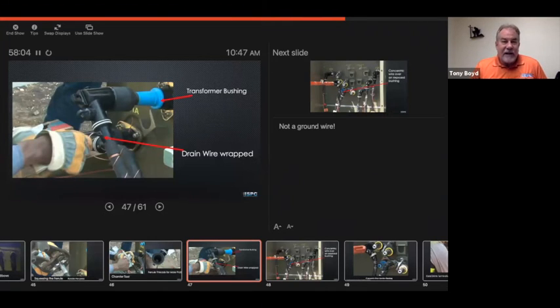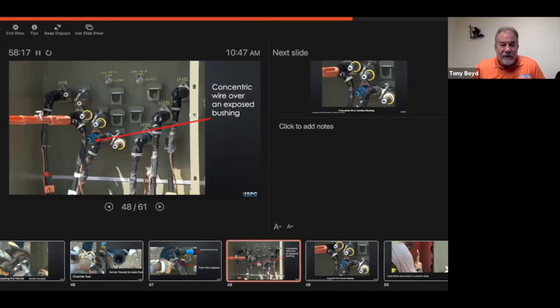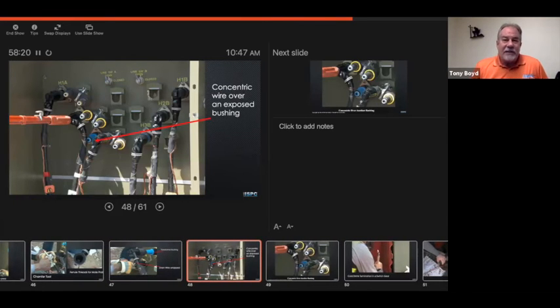There's the drain wire that I mentioned. It gets wrapped around to bleed off any leakage current that may be coming through. There's the transformer bushing that the elbow would go onto. Here is a three-phase pad mounted transformer, and I wanted to bring this out because some of your older transformers do not have switches. This one has switches, which makes everything very safe. We can open and close them, and you can see that these switches are open. So all three of these transformer bushings are turned off.